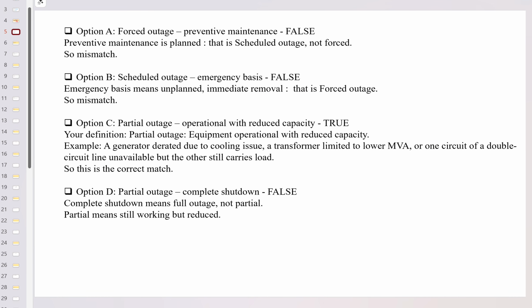Here also I wrote forced outage, that is false because it is preventive maintenance, which is actually planned, so it's incorrect to call it forced. Preventive maintenance is planned, that is scheduled outage, not forced. Scheduled outage is not on an emergency basis. Emergency basis means unplanned immediate removal. Partial outage is operation with reduced capacity. So option C is actually correct.